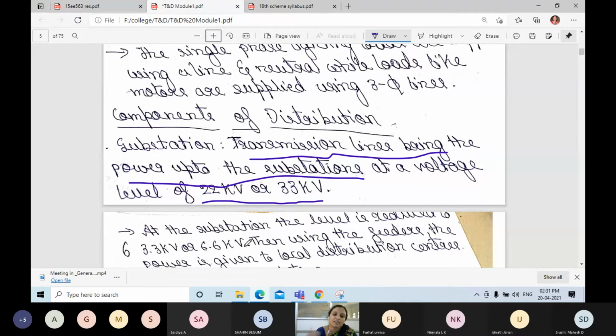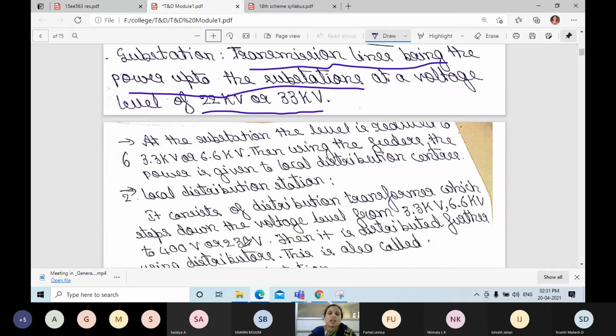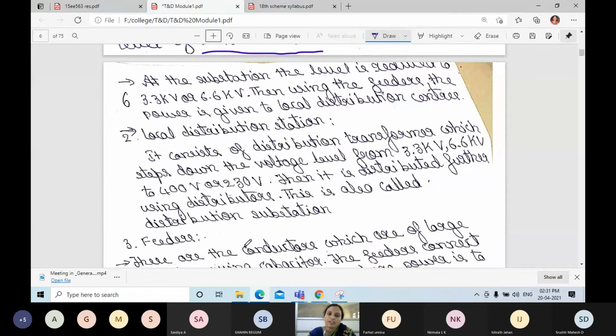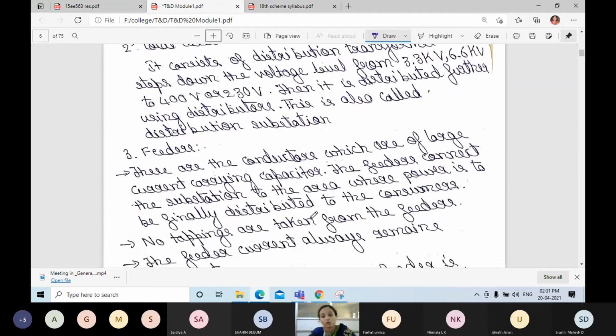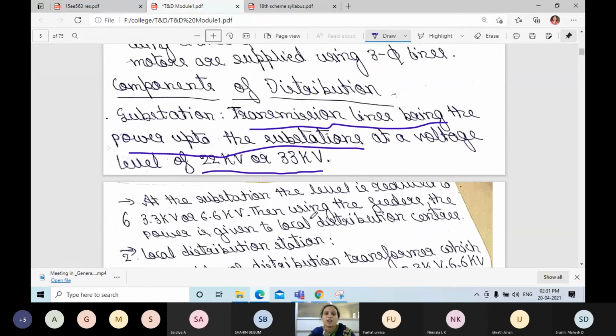Then using the feeders, the power is given to the local distribution centers. What do we get as output from the substation? 3.3 kV or 6.6 kV. Here at the local distribution station, from 3.3 kV or 6.6 kV, it is reduced to 400 volts or 230 volts in this station. Okay. This is distributed further using distributors. This is also called a distribution substation. Next is feeders. This also they will ask. This is important, two questions: the typical line diagram of a transmission and distribution scheme, and the components of a station. Components of distribution.